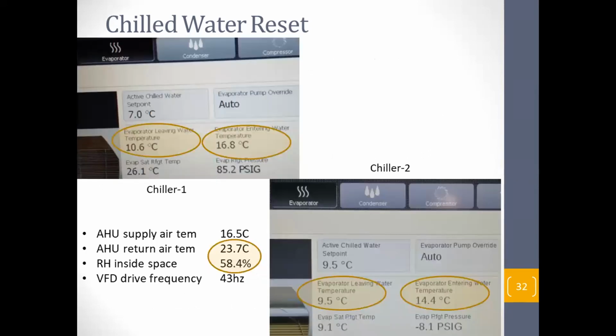So I'll show you an actual setup where there were two chillers operating on a particular day. This is how they maintain their chill water temperature. Chill water is leaving at 10.6. Most of the chiller manufacturers say run at 7 degrees. That is how it has been designed. But they are running at 10.6 and return at 16.8. And at the same time, they maintain overall efficiency at 0.55. That means your air handling unit, chill water pumps, condenser and chiller all manage well. And if we look inside the office, they maintain temperature at 23.7, because this particular building is designed to operate at 24 degrees. And RH is maintained at 58. I think it's okay. Right? 55 plus or minus 5%. So they are operating within the limits.